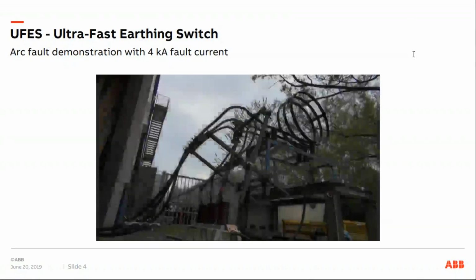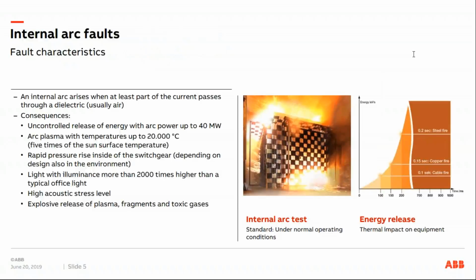So what you could just see was an arc fault. In general, the occurrence of an arc fault is the most serious fault within a switchgear system, and is mostly associated with extremely high thermal and mechanical stresses in the area concerned. An internal arc arises when at least part of the current passes through a dielectric, usually air, such as in the example which we saw in the previous video. The consequences could be, or usually are, uncontrolled release of energy with an arc power up to 40 megawatts.